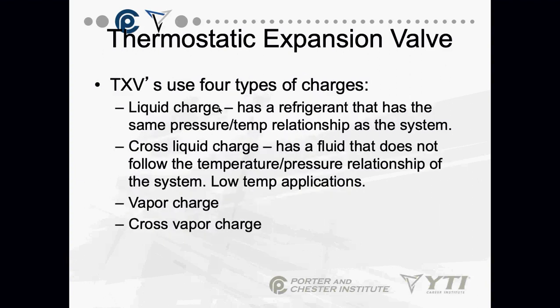Primarily the one you're going to be dealing with is the liquid charge. It has the same temperature pressure relationship, because most of your systems are set up for either R22 or R410A. In refrigeration, we start doing a whole bunch of crazy stuff with TXVs. Now, having said that, are TXVs interchangeable between R22 and R410A? No.